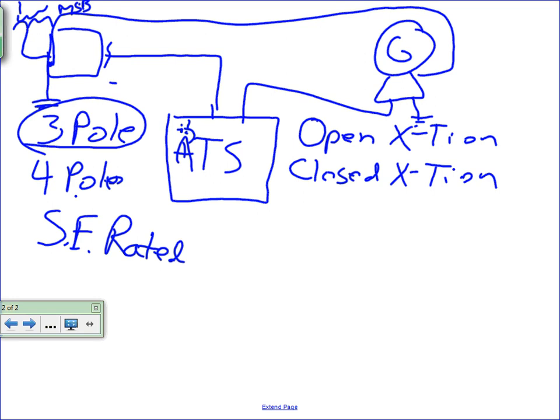Where are you seeing them? Closed transition: data centers, hospitals, somewhere where that second blip is not acceptable, industrial processes. Certain industrial processes, like a glass plant, you lose power, it could screw up hundreds and hundreds of feet of glass where they're just busting it out and cleaning up machines before they can even start up again. So banks, maybe. If it's a run-of-the-mill school or mall, so what if you guys are in the dark for a while? Who cares? It's just the application, right?